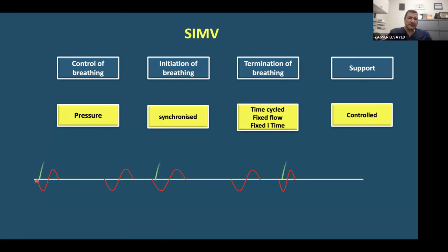So it is synchronized. Once the patient starts to take the inspiration, the machine will synchronize and start the breath. But the end of the breath is not synchronized. So the patient is obligated to respond to the I time from the machine. So it is synchronized only at the beginning, but not for the termination. So control of breathing by pressure, it is synchronized once the infant starts to breathe; it is time cycled, with fixed flow, the I time is fixed, and it is totally controlled.